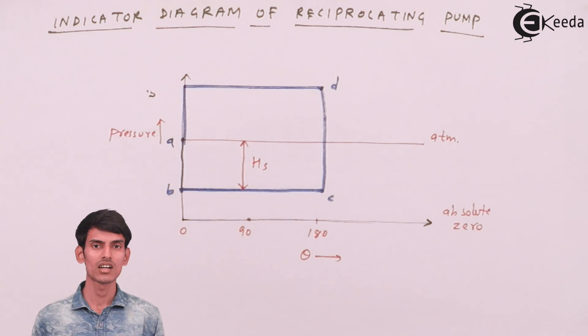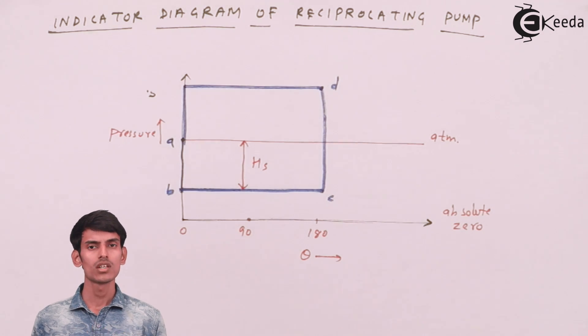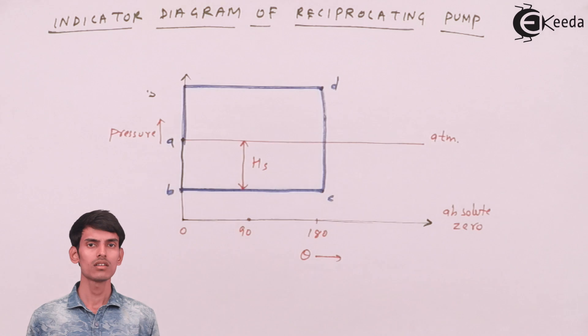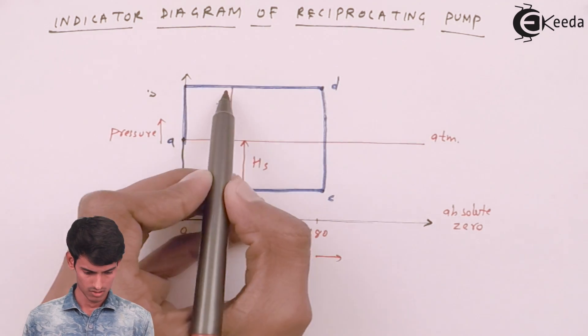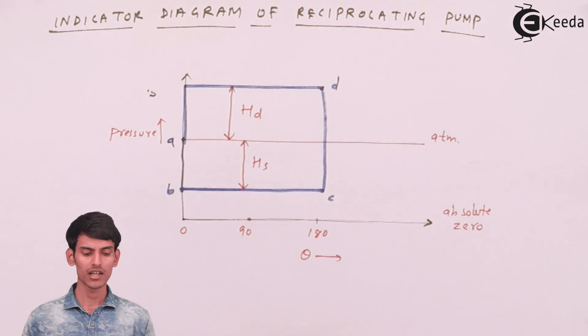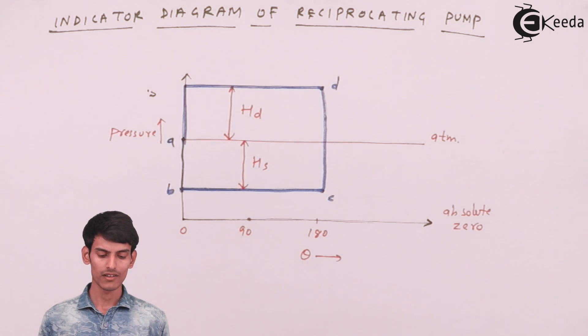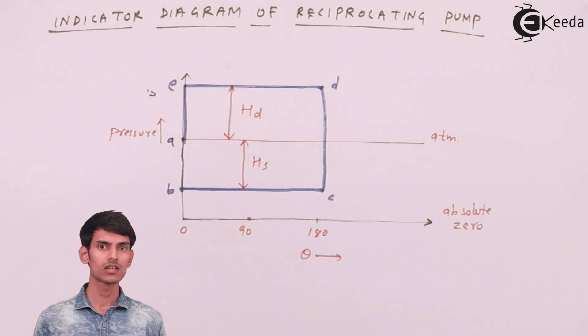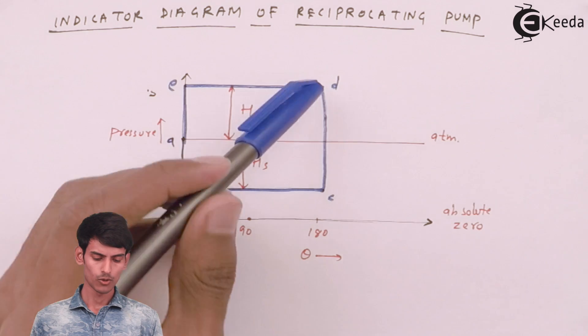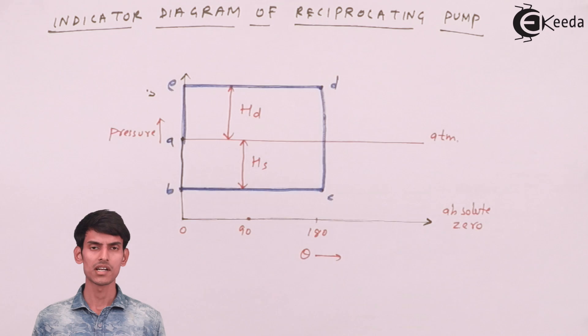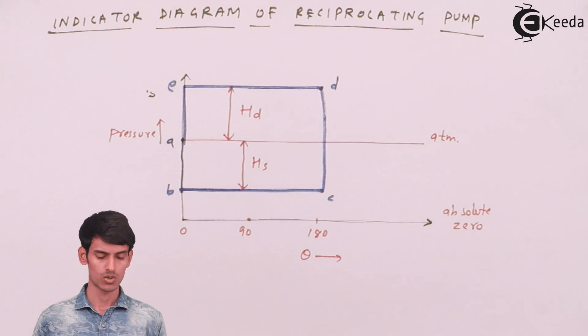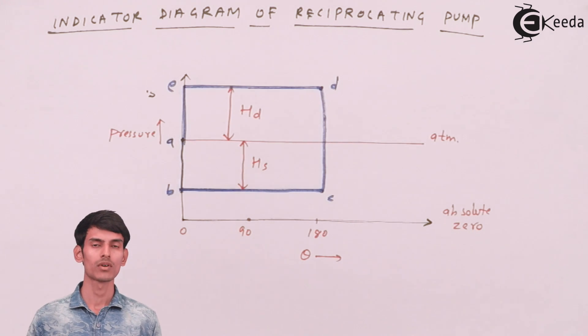The vacuum head created inside the pump must equal HS, and the pressure created during the delivery stroke must equal HD — only then will water be pumped out. So these lengths must be HS and HD respectively. This is the theoretical or ideal indicator diagram for a reciprocating pump. It's important to understand the points A, B, C, D, and E: at A the pressure drops instantaneously by head HS; BC is the suction stroke; at D the pressure instantaneously rises; the delivery stroke runs to point E, after which it returns to A. This is how HD and HS are determined.